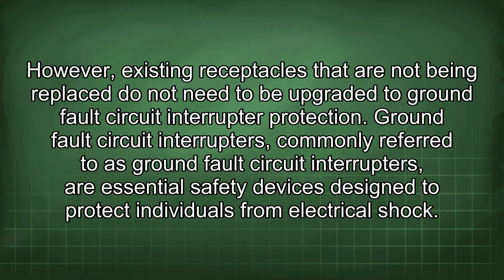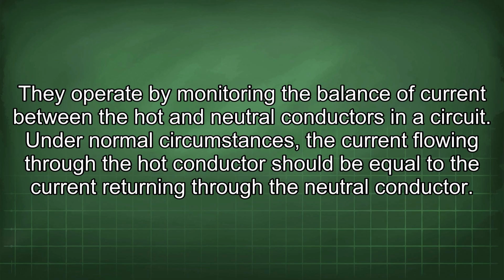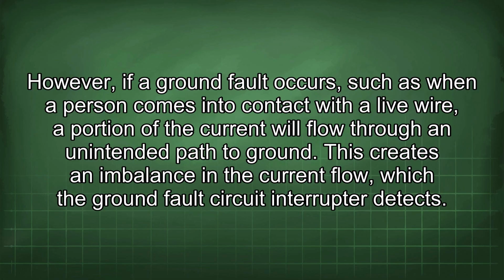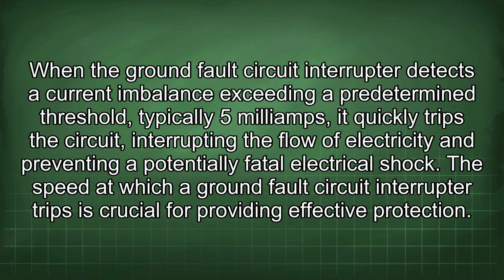Ground fault circuit interrupters are essential safety devices designed to protect individuals from electrical shock. They operate by monitoring the balance of current between the hot and neutral conductors in a circuit. Under normal circumstances, the current flowing through the hot conductor should be equal to the current returning through the neutral conductor. However, if a ground fault occurs, such as when a person comes into contact with a live wire, a portion of the current will flow through an unintended path to ground. This creates an imbalance in the current flow, which the ground fault circuit interrupter detects. When the ground fault circuit interrupter detects a current imbalance exceeding a predetermined threshold, typically 5 mA, it quickly trips the circuit, interrupting the flow of electricity and preventing a potentially fatal electrical shock.